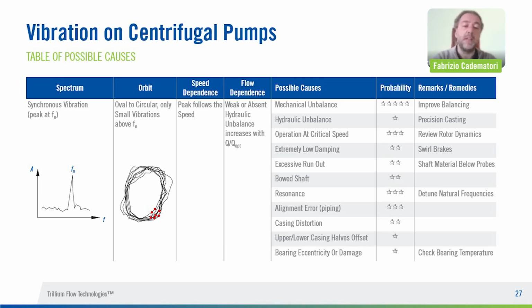If the rotating speed has a limited separation margin with a natural frequency that involves the bearing bracket or foundation, dynamic amplification can happen. And also piping alignment errors or casing distortion can cause a synchronous vibration. Next slide, please.